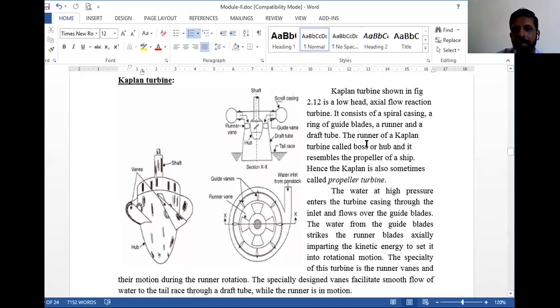Okay, next. The other thing that we have to see is the water flow direction in this turbine. So water actually enters in spirally, surrounding this casing. But what we should see is the starting point of flow: in what direction does it enter before the blade, and in what direction does it leave the blade. So if you look at this, water flows from top, after going around, it goes towards the center where the blades are situated at the lower region. So water falls down onto these blades. Okay, so it enters axially, flows onto these turbine blades and leaves the turbine axially itself.